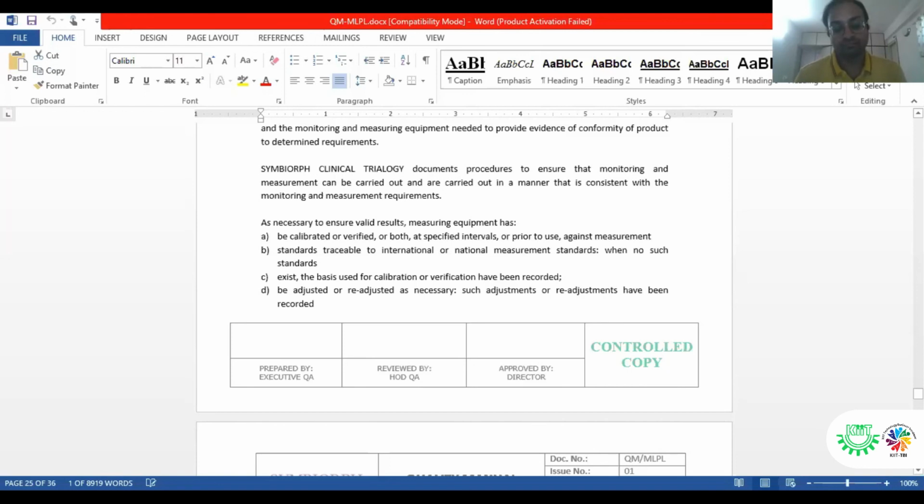Okay. That means prototype development within a fabrication lab or with local manufacturing is not going to help. No, yes, it will help, but you have to cross-check whether the company where you are doing all the fabrication activities is complying with that requirement or not. With the basic requirement of ISO 13485. In that case, the whole requirement is not going to be applicable. Only some of the departments or some of the things will be applicable to them, and some will be to you. You have to cross-check with them.